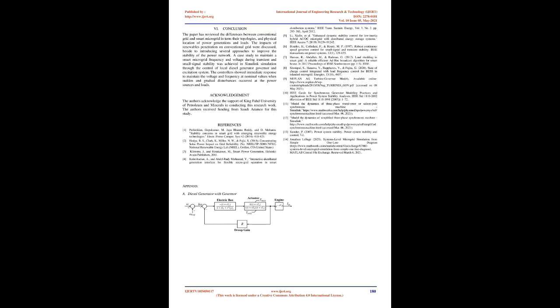In [8], the engine is simply represented with a first-order system, where the governor actuator and controller, electrical box, are represented as third-order and second-order systems respectively, refer to Appendix A. The range of model parameters can be selected as specified in [9]. The objective of the governor is to maintain the machine speed/frequency at the nominal value by controlling the fuel consumption through valve opening and closing.